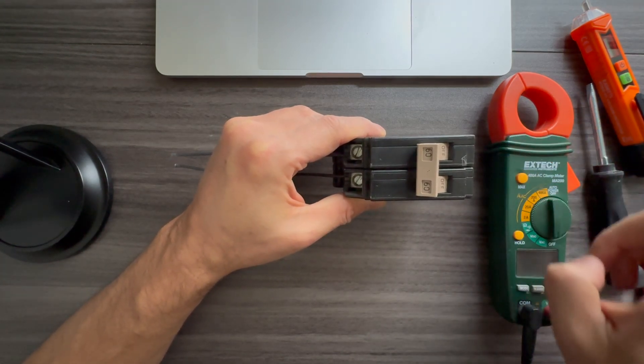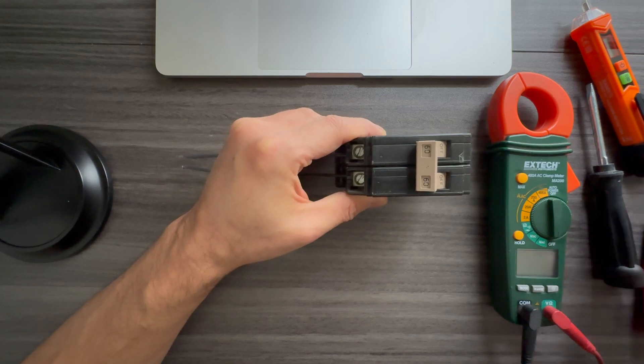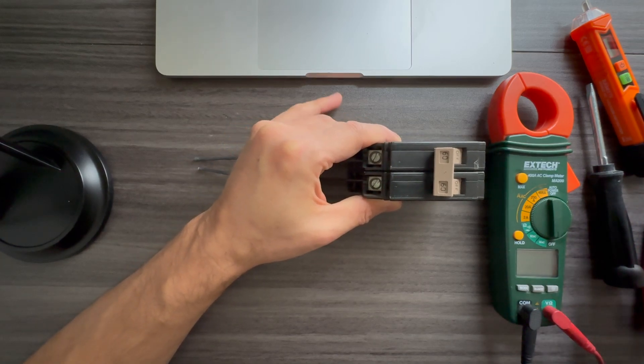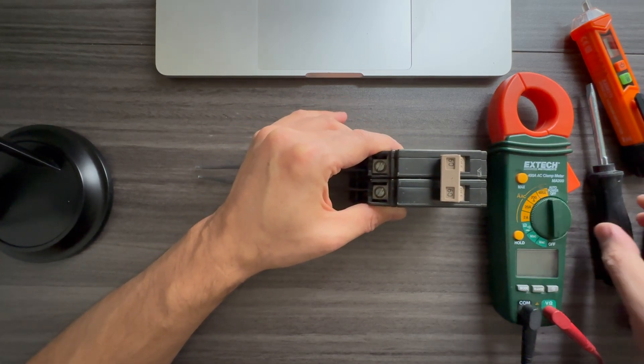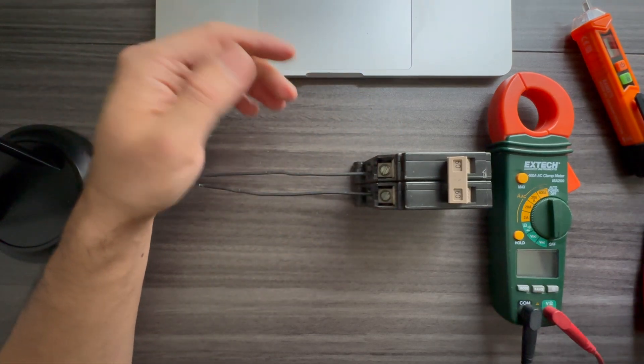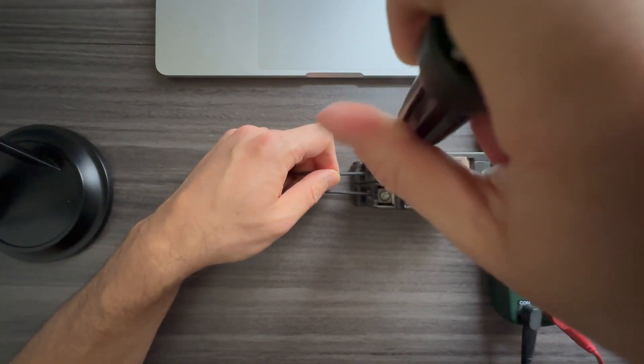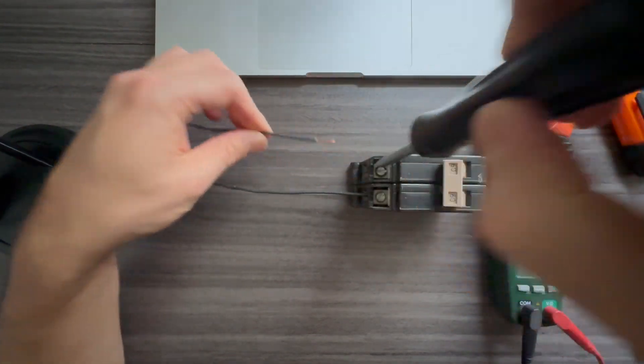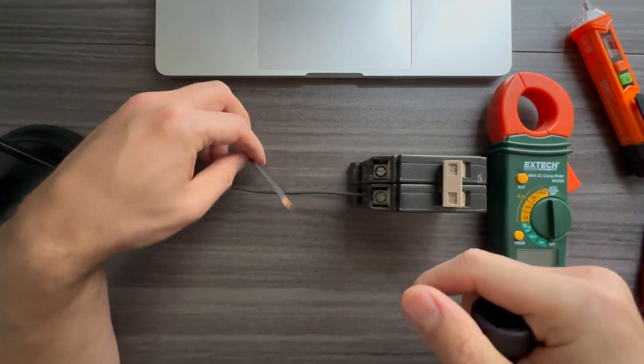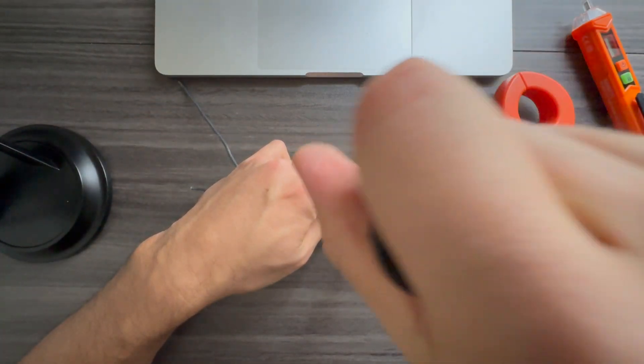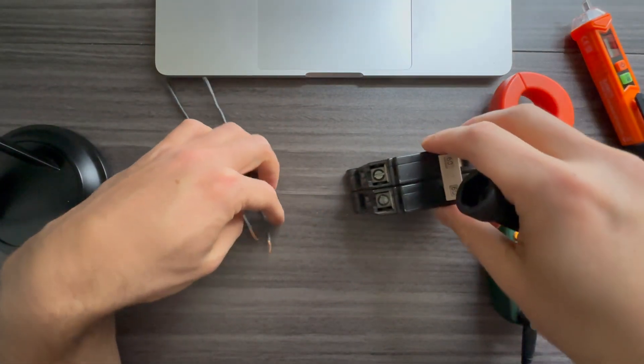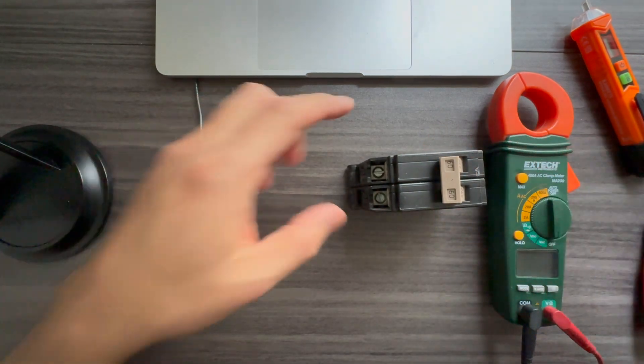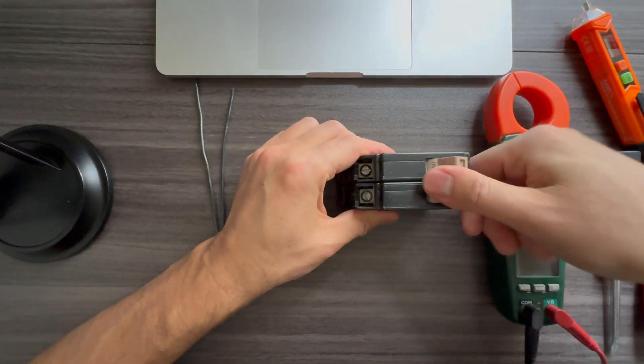You see, you hear this clicking sound and then it goes right back. So usually what that means is you have a short in the circuit. To know 100% if that's the case, what we can do is just remove the wiring, put a wire nut, set it aside on the panel.